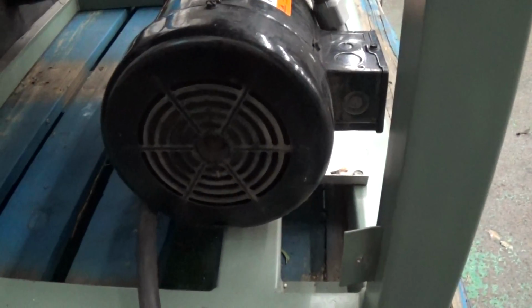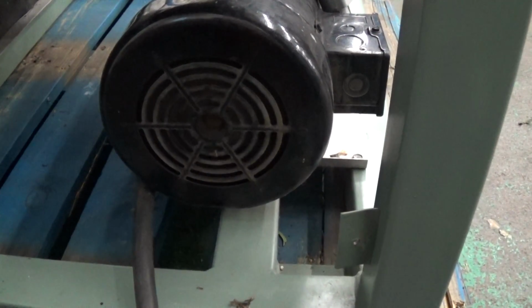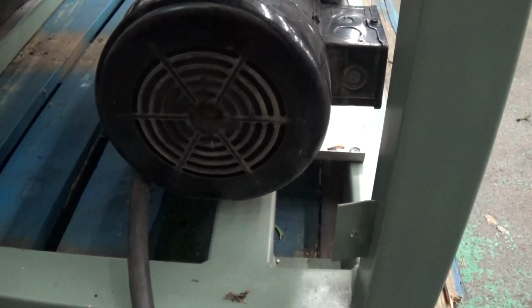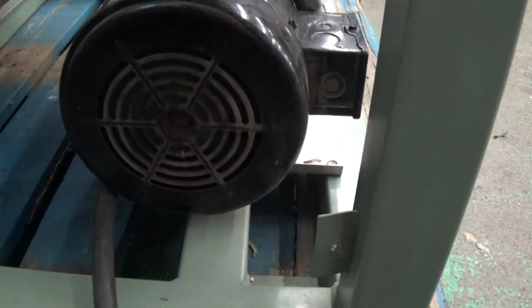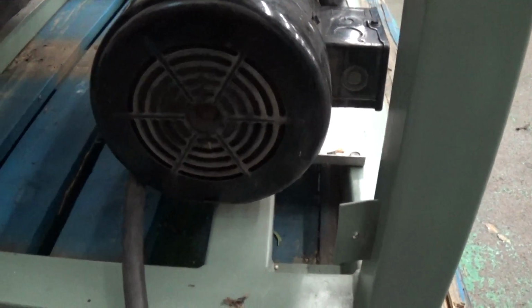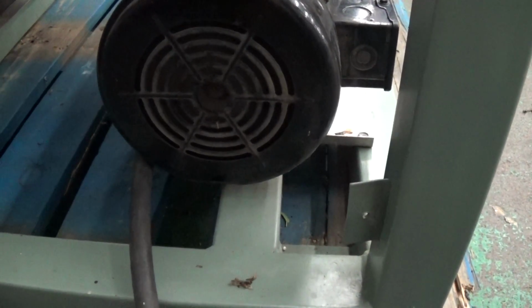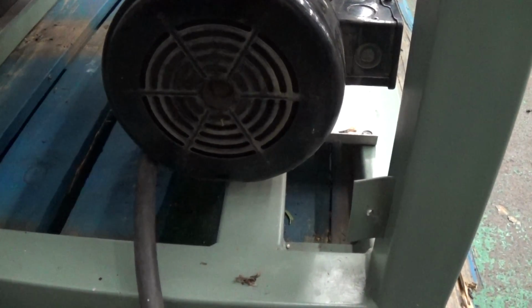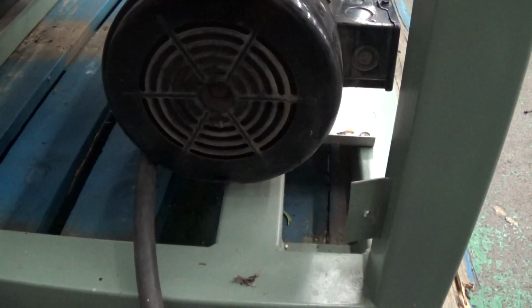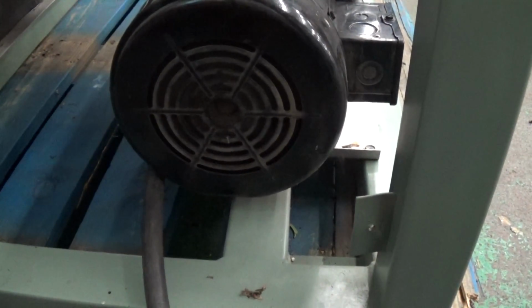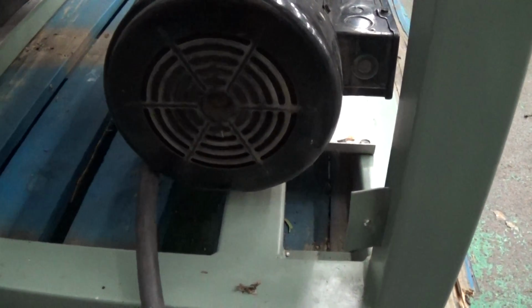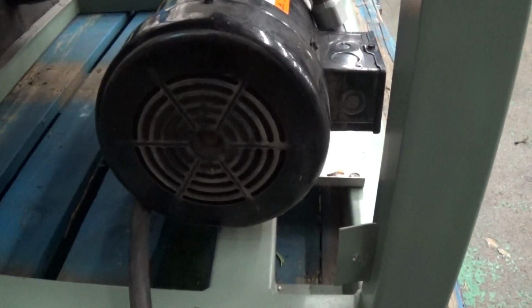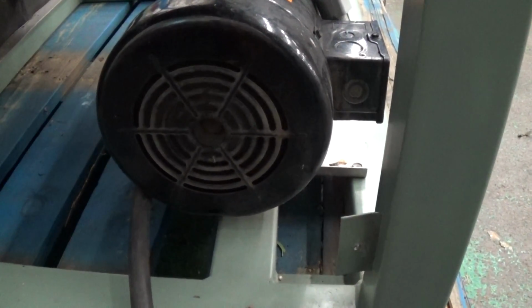So getting back to the pump here, you saw the rotation arrow. When you bump the pump, you want to have somebody back here with a flashlight, and you just bump it really quick to make sure you have the right pump rotation. If you don't, you change any 2 legs of an incoming 3-phase power, and if you have to do that, make sure again about the wild leg going to the controller transformer.